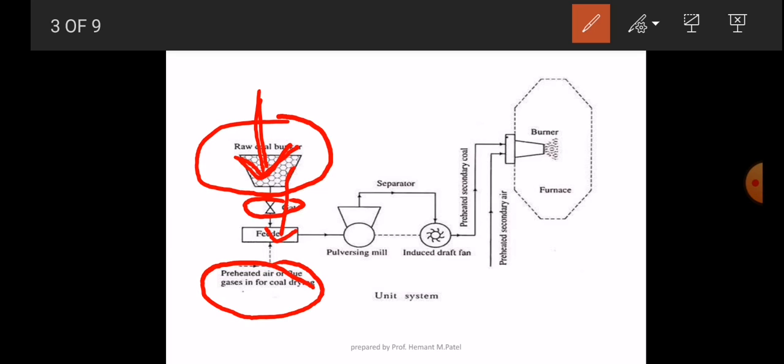Preheated air is used for the dryness of the coal, because we all know that if moisture contents are present in the coal, the combustion efficiency is reduced. That is why we use dry coal in the furnace. So preheated air is supplied into the feeder for the drying of that coal. After that, the coal goes into the pulverizing mill.